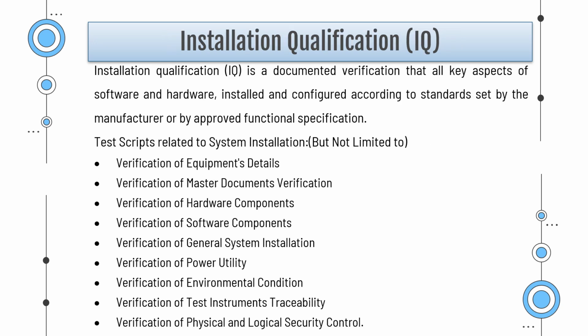Installation Qualification. Installation qualification is a documented verification that all key aspects of software and hardware are installed and configured according to standards set by the manufacturer or by the approved functional specification. Test scripts related to system installation, but not limited to: verification of equipment details, verification of master documents, verification of hardware components, verification of software components, verification of general system installation.